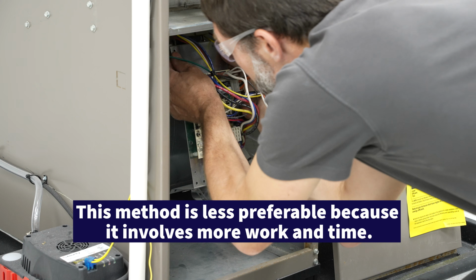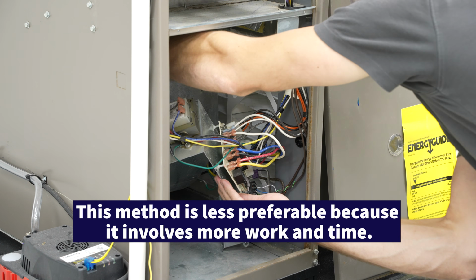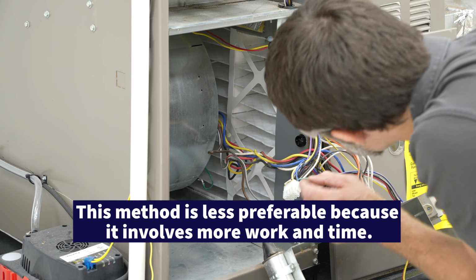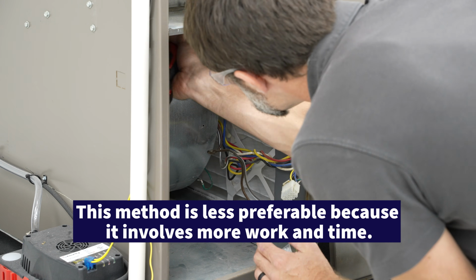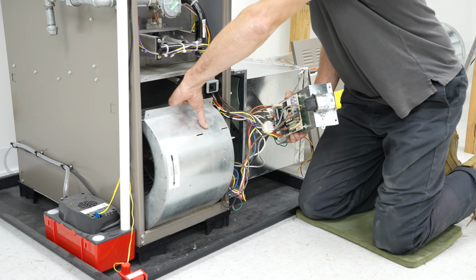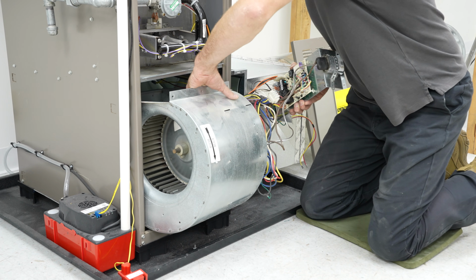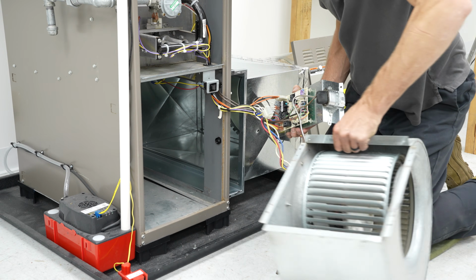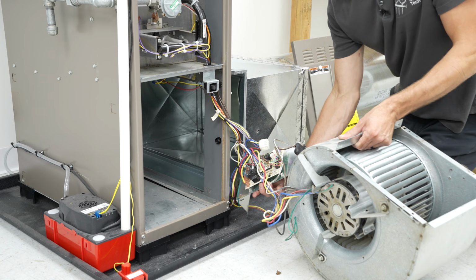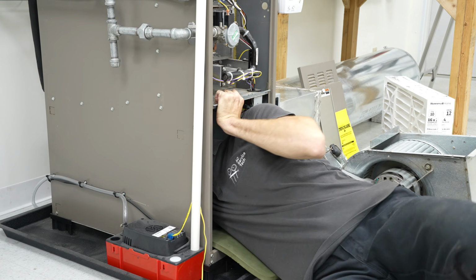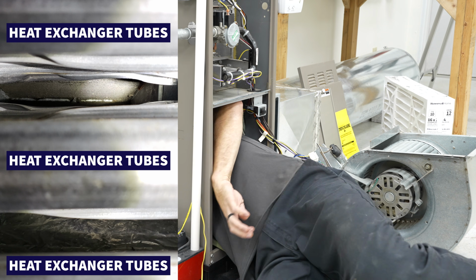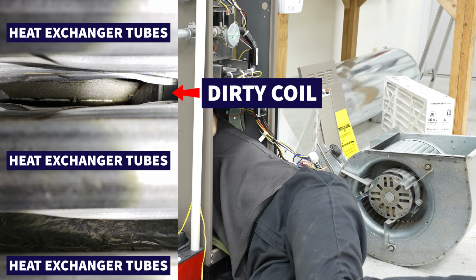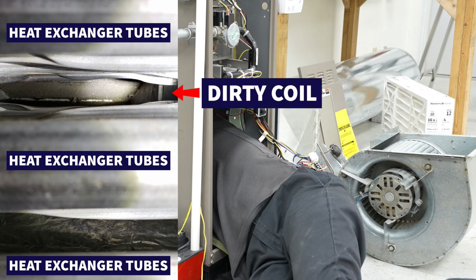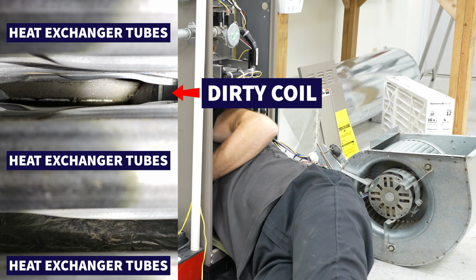I'm first going to remove some of the terminals and the Molex plug, and then pull out the electrical panel, and then unscrew some of the screws that hold the blower motor in place, and then pull that out of the way, and then I can get in there and fit in there and take a photo or a video upwards past the heat exchanger coils up to the bottom side of the evaporator coil to see if it's clogged. So in this case you can see the dust on there, so you can see that it is clogged.